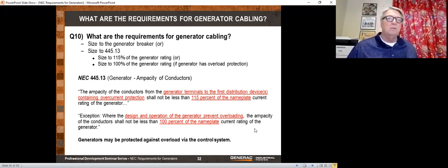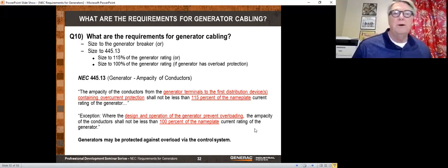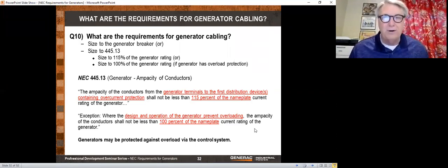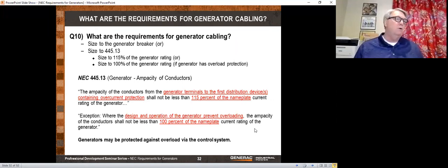You have three choices. Number one, you can size the wire according to the circuit breaker, or you can size the wire to 115% of the generator rating, or you can size the wire to 100% of the rating if the generator has overload protection. Now, all of our generators have overload protection. And so just to give you an example, let's suppose that you have a 500 kilowatt generator. The full load amps on a 500 kilowatt 480 volt generator is 752 amps. It's going to have an 800 amp breaker in it.